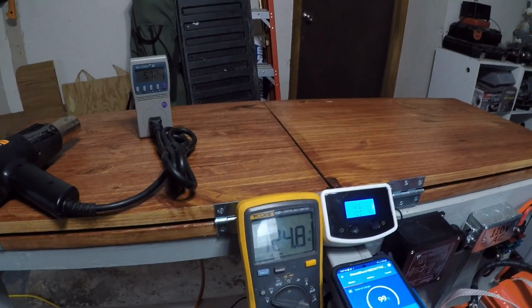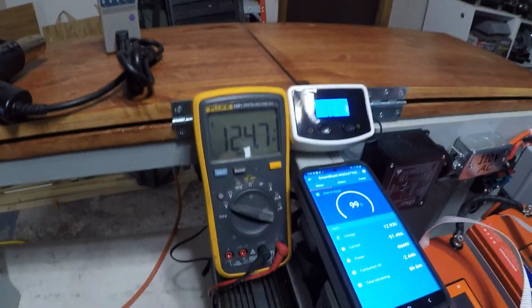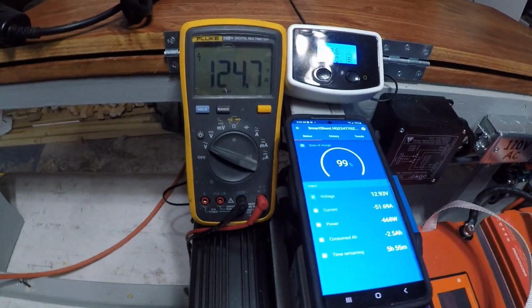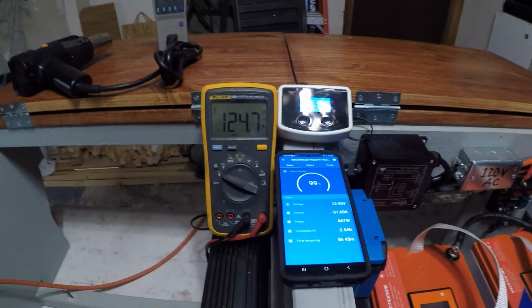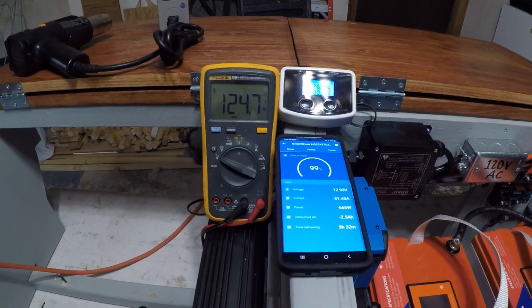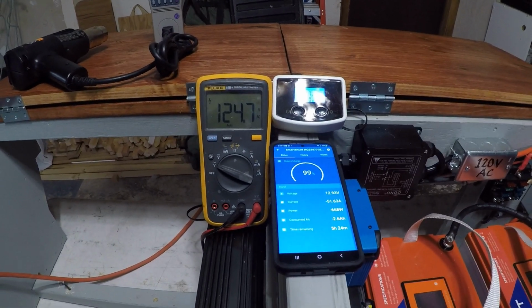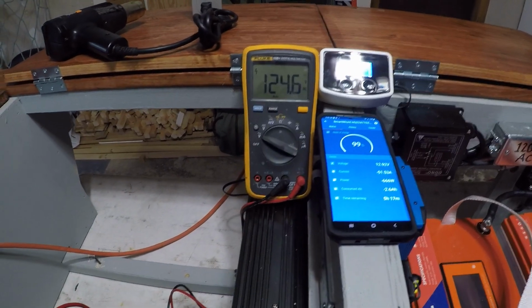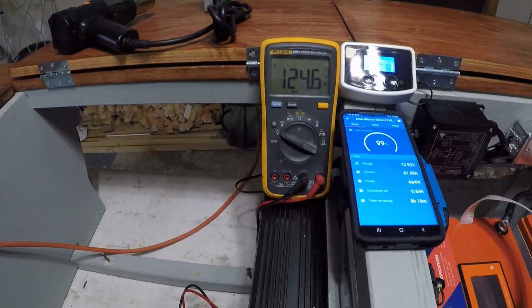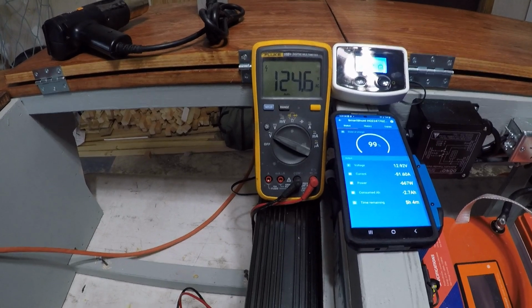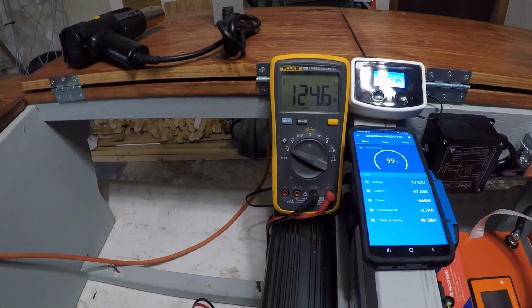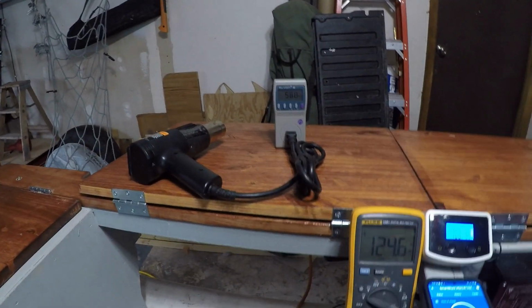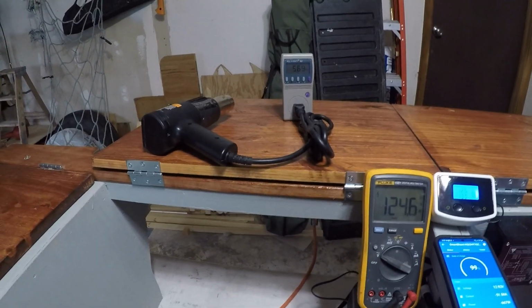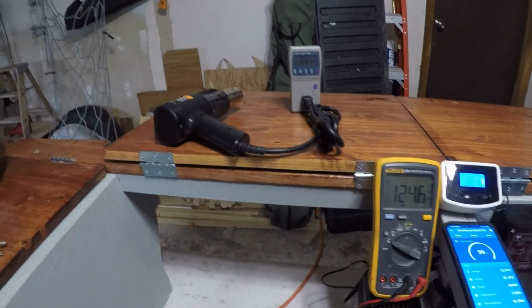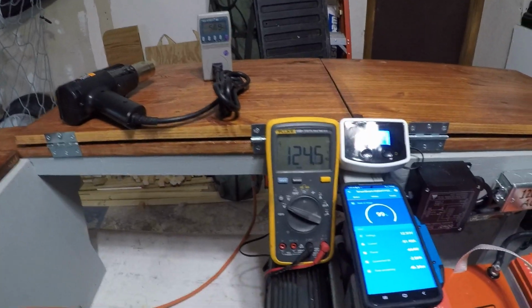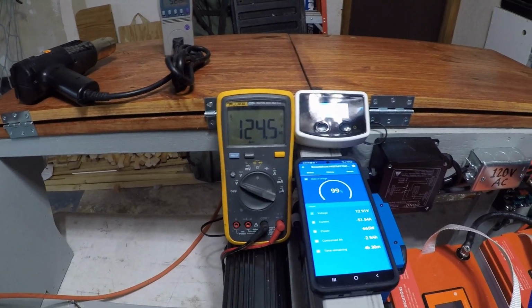Inverters are not 100% perfect. At best you get about 85% of what they're rated at, because the inversion process uses up quite a bit of power. So we've lost almost 100 watts. We're outputting about 100 watts more than we're actually getting at the outlet. It's simply going to be wasted because this inverter is going to get nice and warm, and all that extra stuff is going to be radiated away as heat.